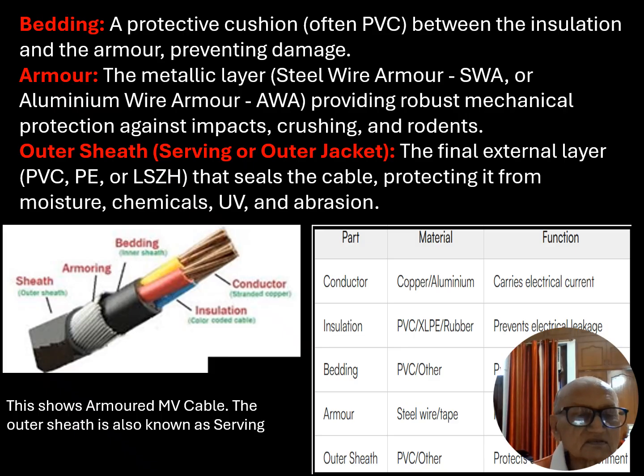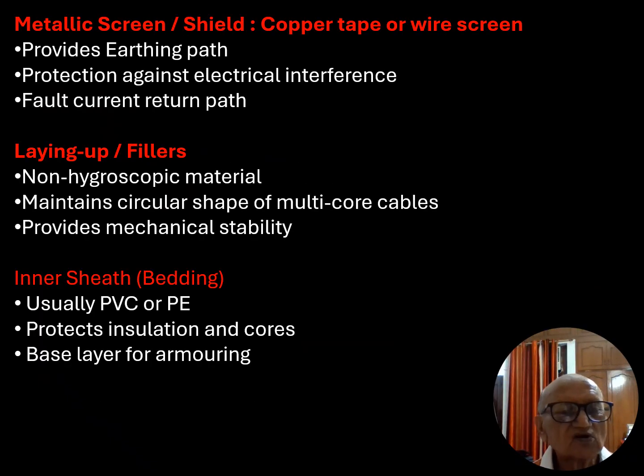The outer sheath, also known as serving or outer jacket, the final external layer in case of PVC, PE, or LSZH, seals the cable, protecting it from moisture, chemical, ultraviolet, and abrasion. The outer sheath is also known as serving.